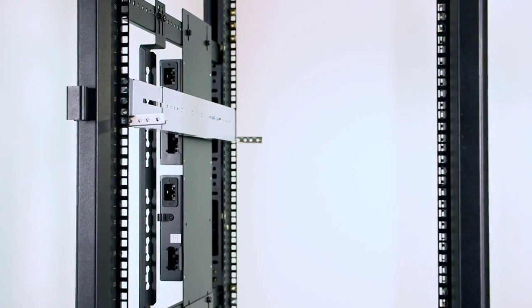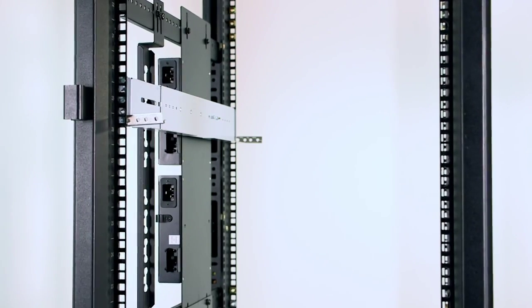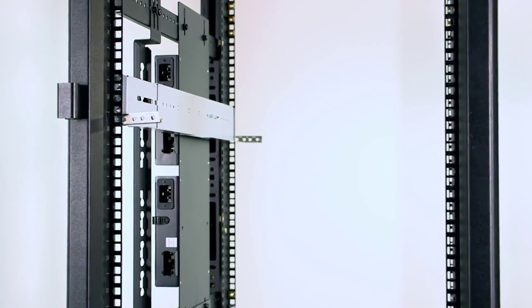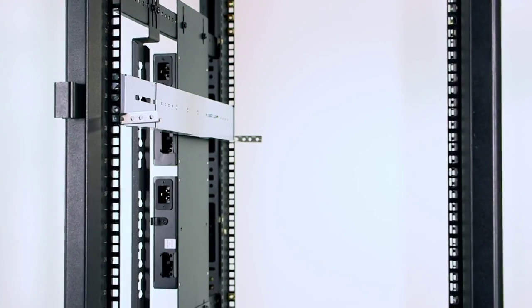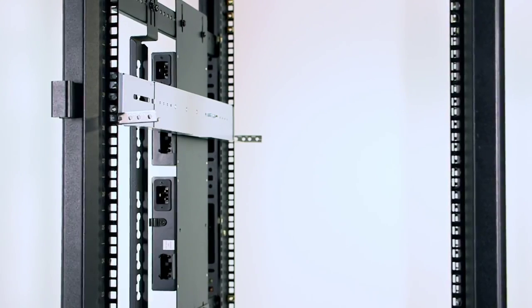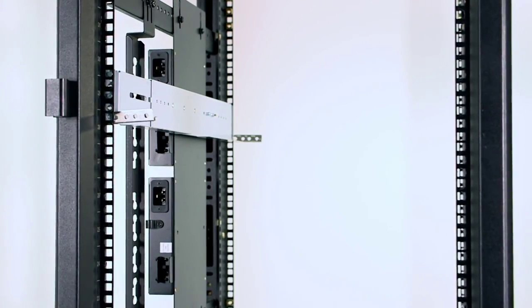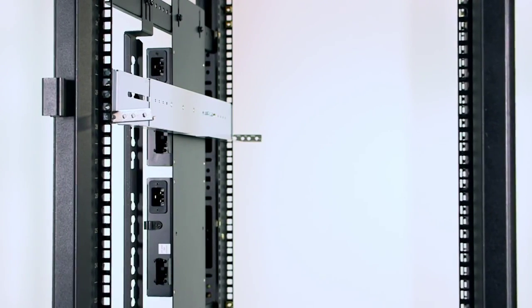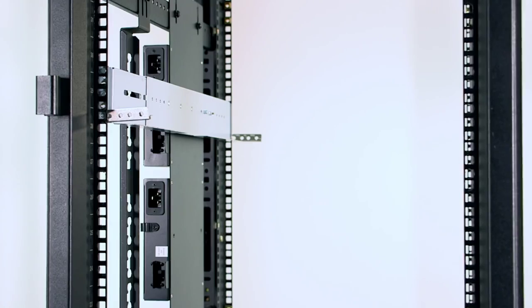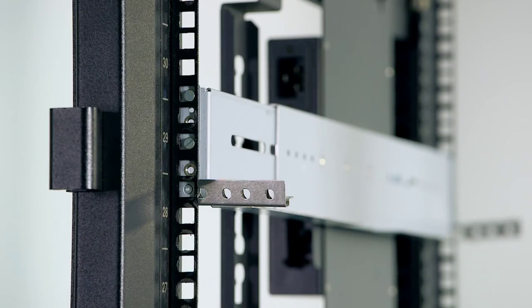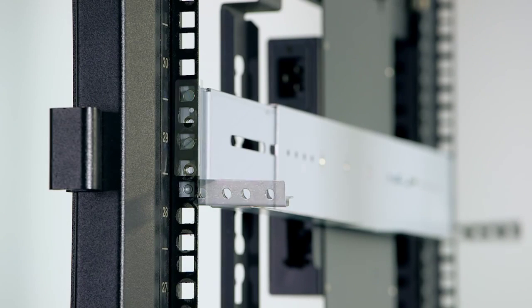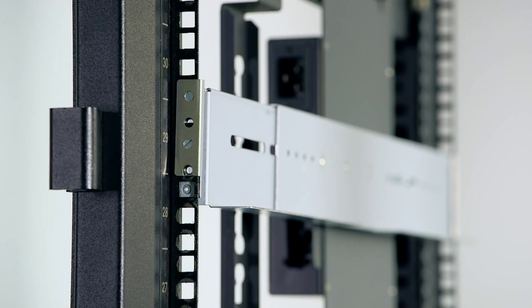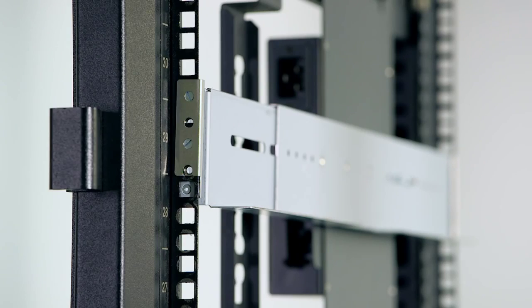Make sure that the rails are aligned on the inside of the rack cabinet before pressing the two bracket pins into the holes of the rack. Repeat this process on the front of the rail. When you are finished, close the rear and front hinge brackets to secure the rack to the rack cabinet.